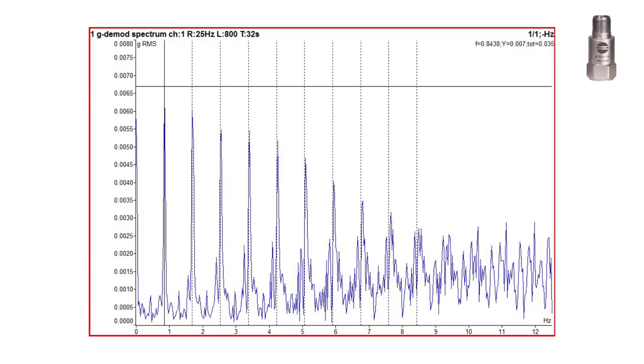And it really helped. You can see the repeating frequency 0.85 Hz and its harmonics. The harmonics always occur because the enveloped signal is distorted.